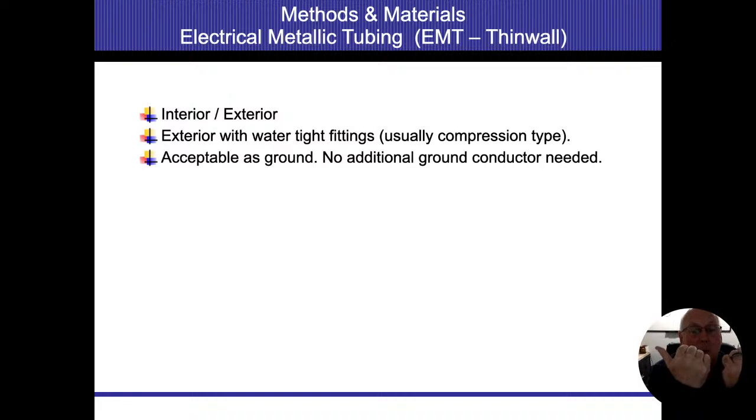So the conduit is more than just protecting the wire and the convenience of pulling wires through it. That's my ground path. So making sure that those are connected, I can't stress that enough. Without it, if I do have a ground fault on the load side, there's no way for me to trip the breaker. Everything's going to be energized. And if somebody touches that and they have another ground path, whether they're barefoot on the concrete or water or touching plumbing pipes, the electricity will flow through them.